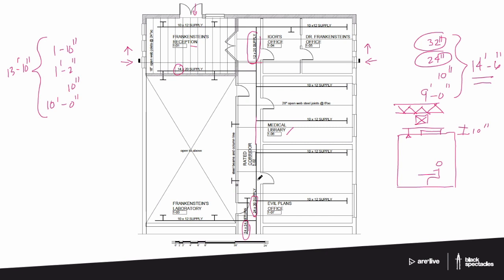I have a number of questions here about the orientation of the duct. Yeah. So some folks maybe aren't comfortable with the idea that the 24 by 30, that you're not taking, like, why aren't you taking the 30-inch height, right? Why are you assuming that it's the 24, the shorter height? That's a very good question, and the answer is because I want to. If you think about it, why would I ever make it harder on myself? So there is no reason to make it 30 inches tall. The only thing that's going to do is make my building taller and cost money.